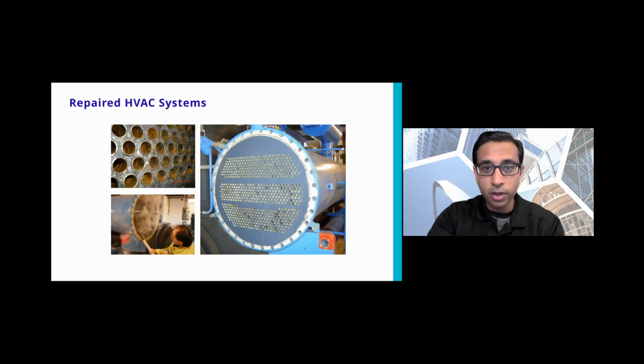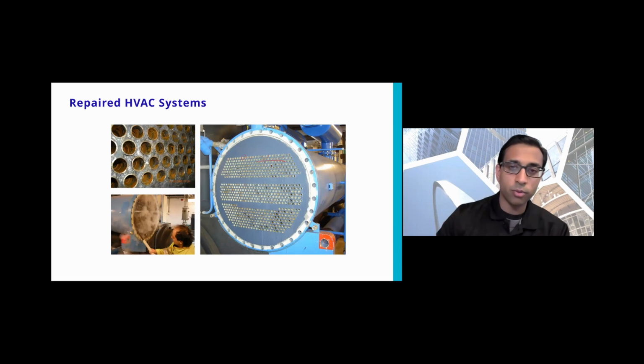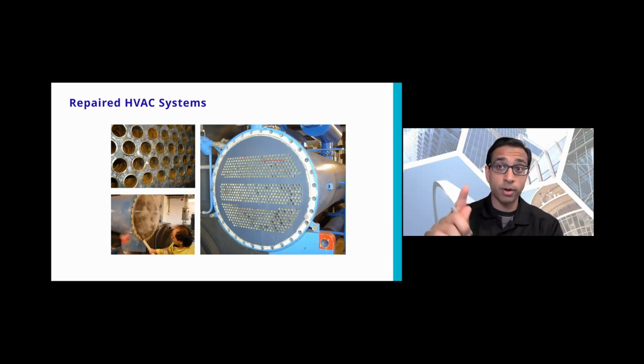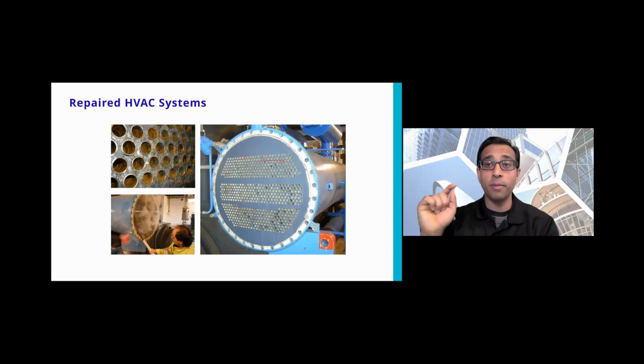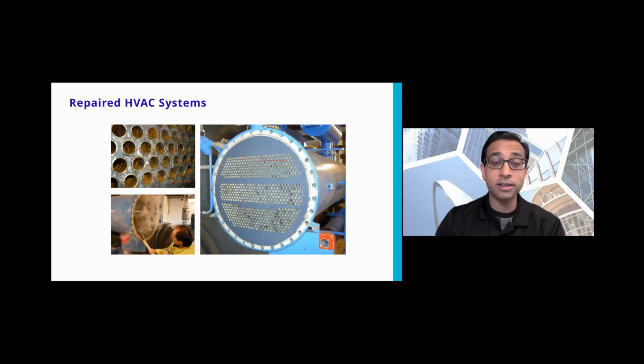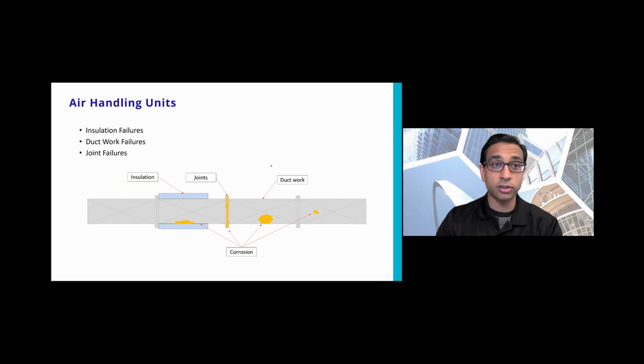We'd actually put a cork in every one of these holes, right? You'd have corks throughout this whole thing, and then you'd fill it with the epoxy metal. Once you fill it with the epoxy metal, remember I talked about the ceramic coating—now you put the ceramic coating on top of the metal coating, and that extends the life of that exchanger. That's a good chiller. It's going to last a long time.